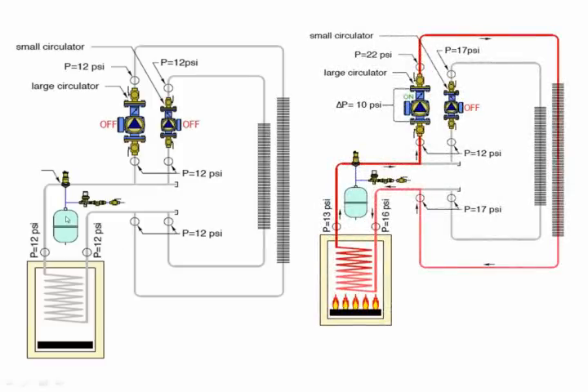There's a call for heat. The pump fires on, and let's find out what happens to our pressure. Now, remember I told you the reference point to start calculating pressure is your expansion tank, not calculating, but what actually takes place. We start off with 12 psi, and that's where we start off here, 12 psi, and assume there's very little pressure drop through our headers over here. So going into our pump is 12 psi. Our pump raises it 10 psi of head, so we've got 22 psi on this gauge coming out.